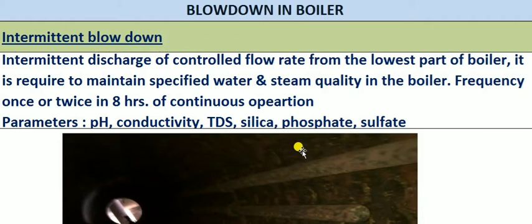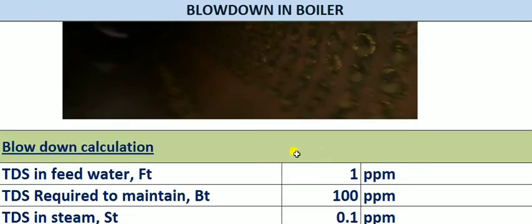Intermittent blowdown normally operates once in 8 hours. In the worst case, once every 4 hours, based on our water quality achievement. It is not a continuous operation. The intermittent blowdown comes from the lowest part of the boiler — that is from the mud drum. There is a drain line from the mud drum through which it operates. The valve will not be continuously fully open; it will be throttled during operation and varied based on the requirement.